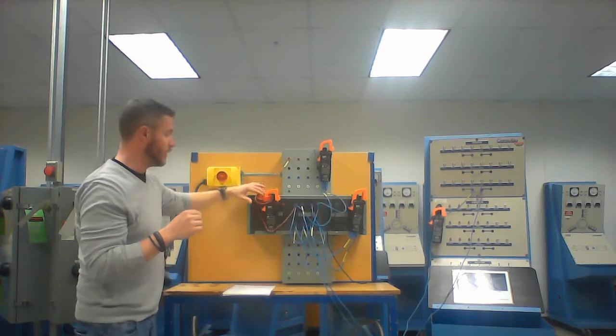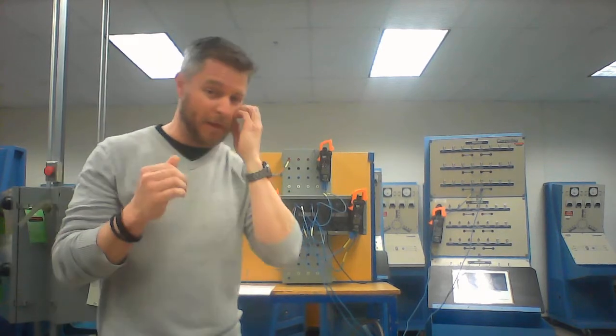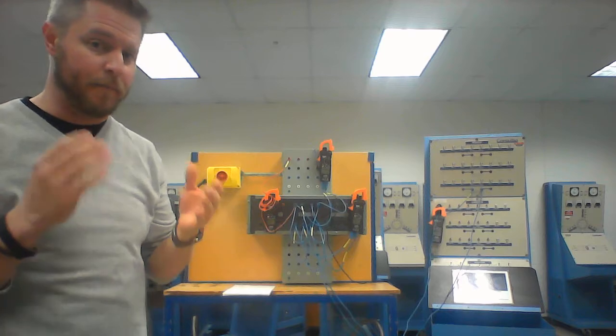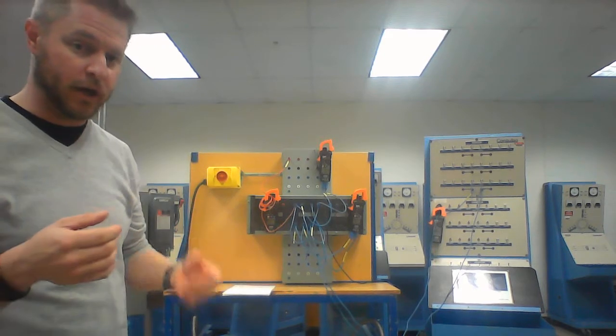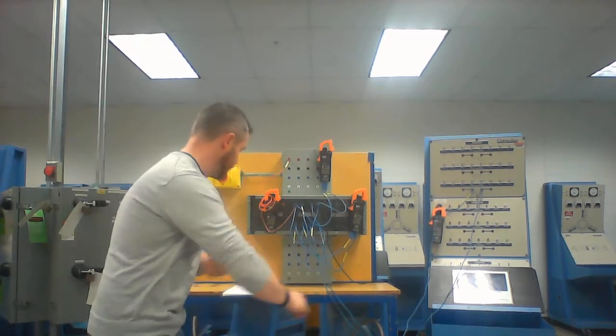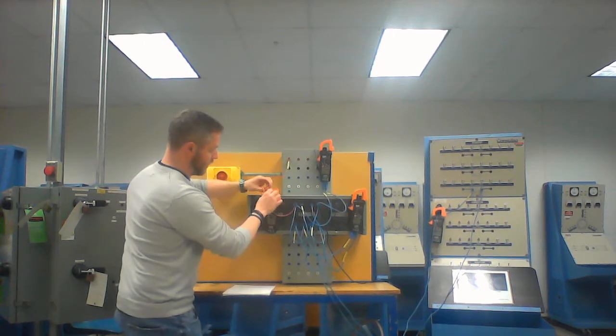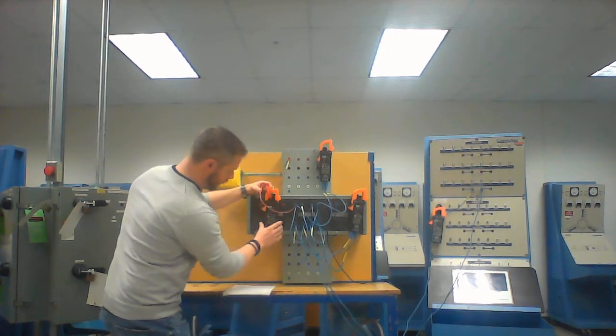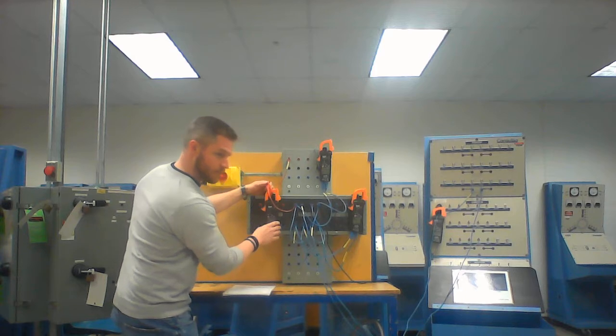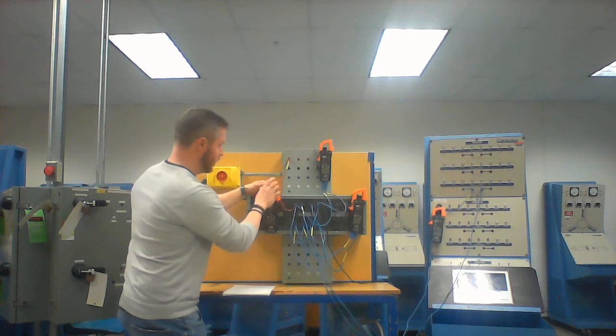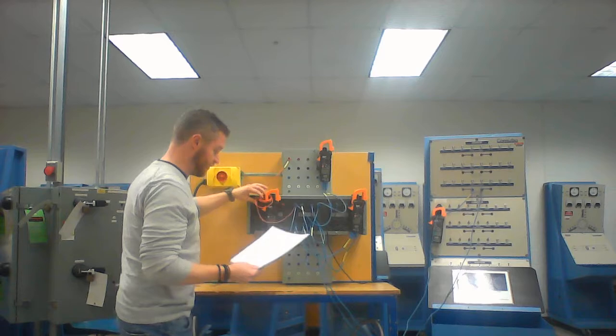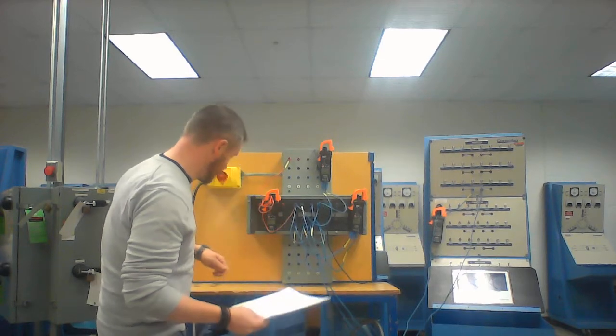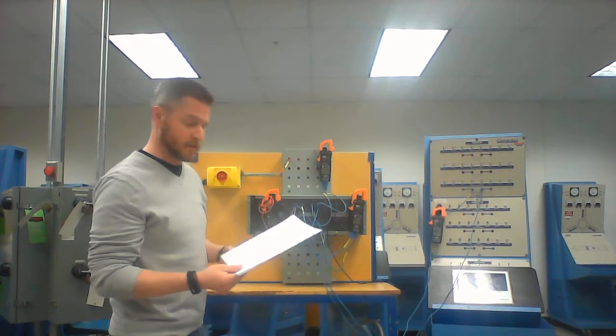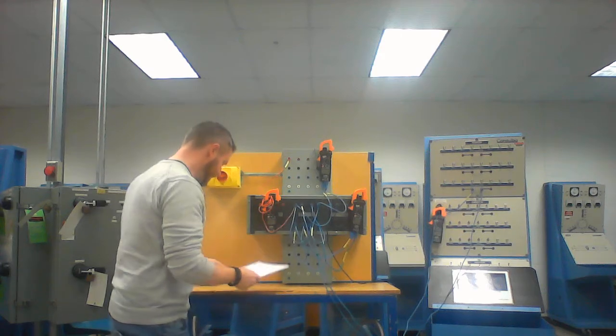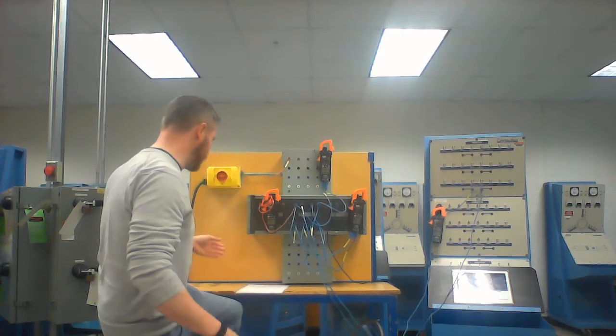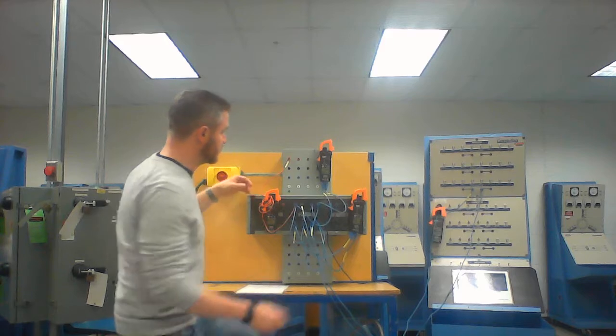The reason why I put that coil on there is that these meters aren't really that awesome at measuring 0.1 amps, which is pretty much what you're going to calculate out to be for your excitation. But if I put a 6-turn coil through in there, or a 10-turn coil, whatever value I see coming from the meter, I just divide it by how many turns I have. So my excitation current for step number 3, my meter reads 0.63, so you're going to be around 100 milliamps, somewhere in there. Then it says for step number 4, measure and record primary and secondary voltages.